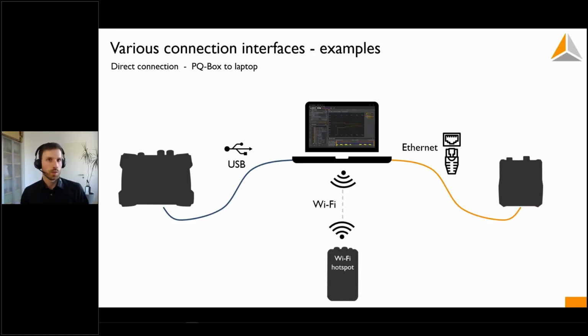And you can always go wireless as well. Therefore, the PQ-Box needs the Wi-Fi package. The PQ-Box 50 always comes with Wi-Fi. For the higher models, it's optional because they also do have an Ethernet socket, but you can connect to the PQ-Box hotspot. So the PQ-Box 50, for example, or 150, doesn't matter, generates a Wi-Fi hotspot, and then you can connect with your laptop to the PQ-Box. Open WinPQ-Mobil, then you have to set up the TCP/IP connection with the connection manager, and off you go. You will find all this in the user manual as well. So this is a direct connection from one device to the other device.